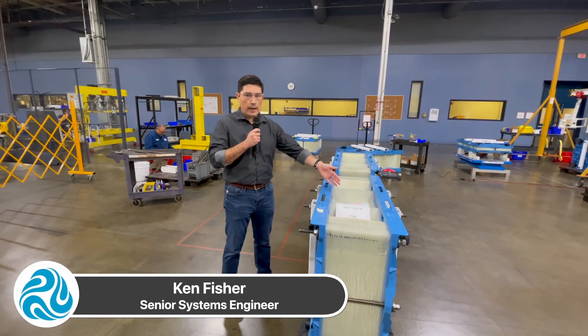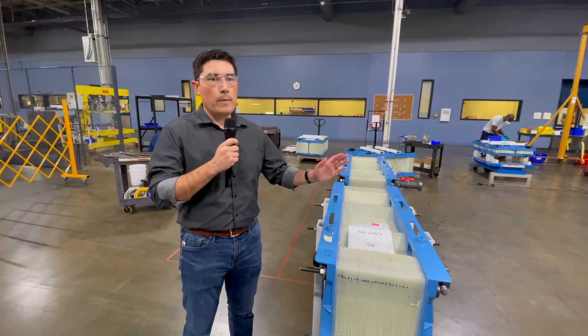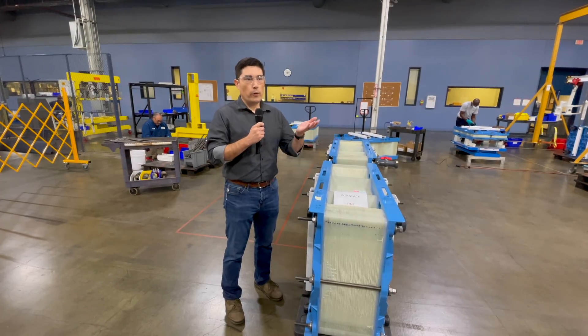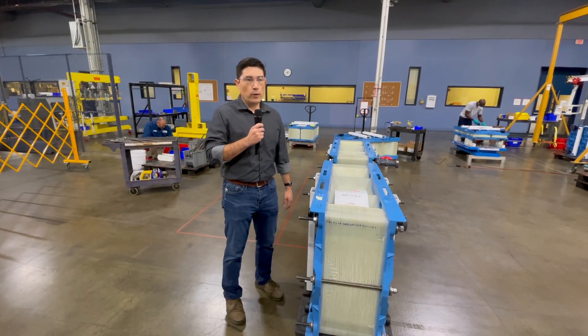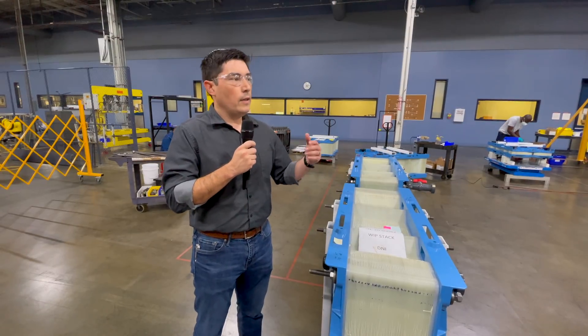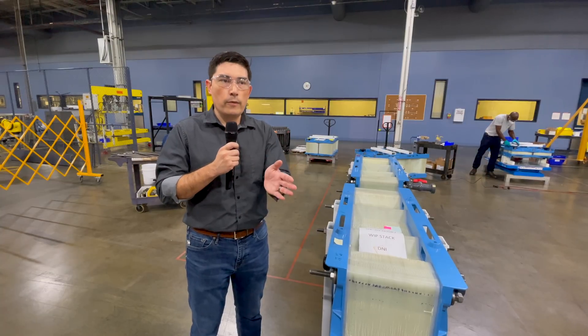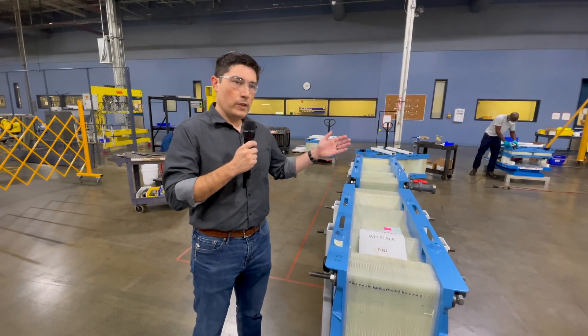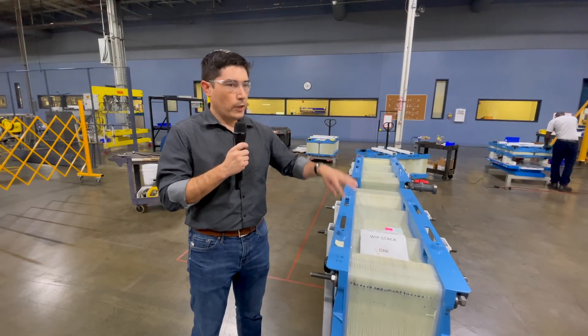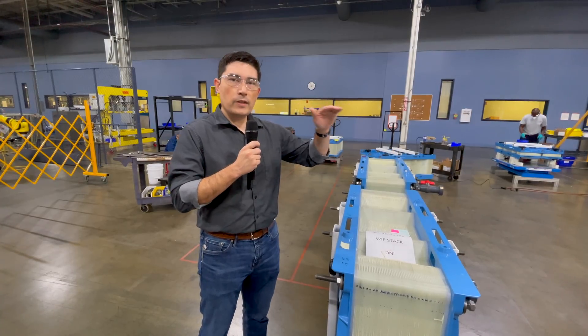This is one of our 50-cell stacks. Each cell runs an open circuit voltage around 1.1 volts. Because it's a flow battery, we don't connect them in series to get to high voltage levels. We pass that through a DC-DC converter to boost the voltage from the stack voltage up to 850 volts DC. With a lithium system, they stack cells in series to get up to 1,000 or 1,200 volts, which means when the voltage sags, that whole range drops down. Because we're not stacking them in series, there is no sag at the high voltage level — that stays very stable.